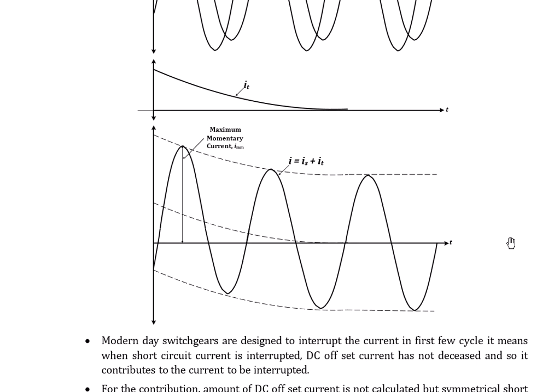Okay, so how can we design our switchgear? Modern day switchgears are designed to interrupt the current in the first few cycles. It means that when the short circuit current is interrupted, the DC offset current has not decreased, and so it contributes to the current to be interrupted. The contribution amount of DC offset current is not calculated, but the symmetrical short circuit current alone is calculated, and then the value is increased by a multiplying factor to account for DC offset current. So we have to take care of this DC offset current.